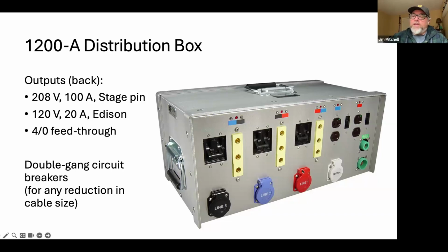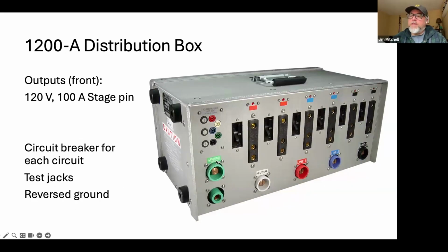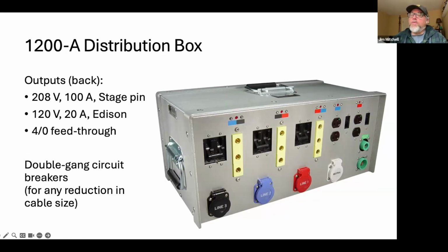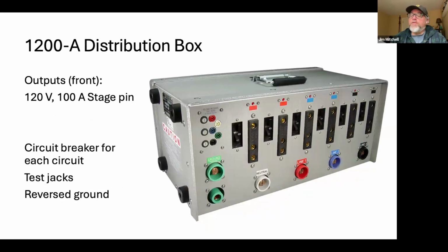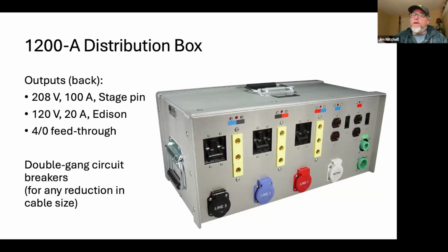I was going to point out, in addition to the yellow coating on these receptacles, if you could flip the box around, you can see that the spacing is different on the plugs. On the 120 version, the neutral and the ground are closer together, and the hot is set aside. Whereas on the yellow one, they're spaced a little differently, so you can't accidentally take a 120 cable and plug it into a 220 cable, which could be exciting for all the wrong reasons.